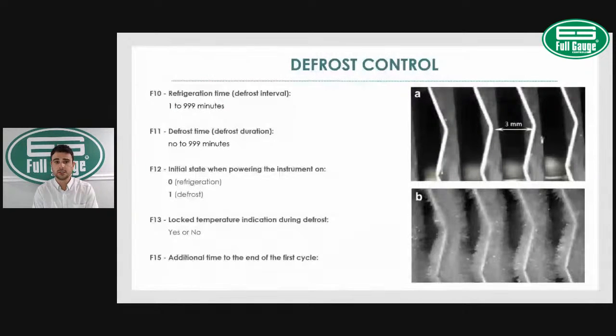Lock temperature. Lock temperature indication during defrost, yes or no? So this allows you to lock the last temperature reading during your defrost cycle. And this actually prevents those false service calls.